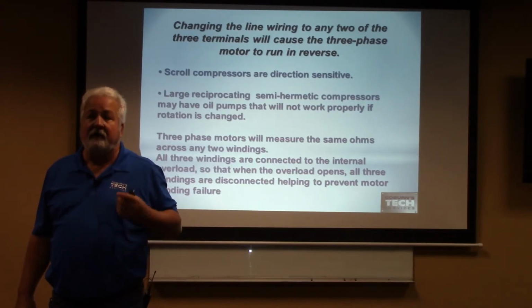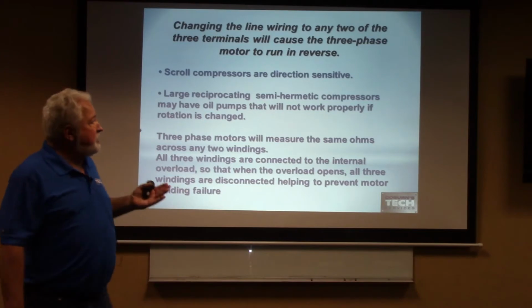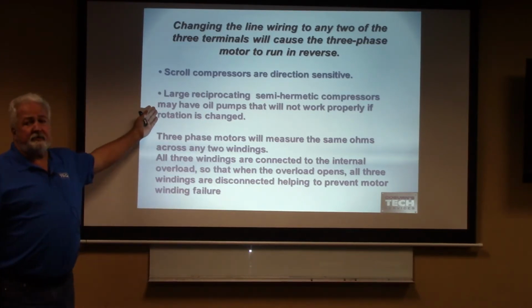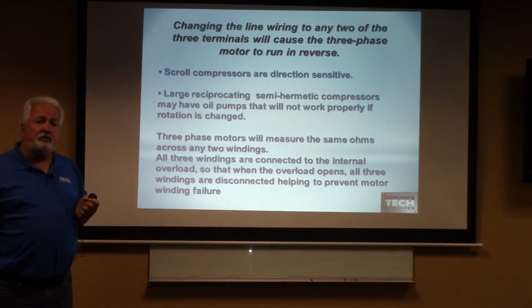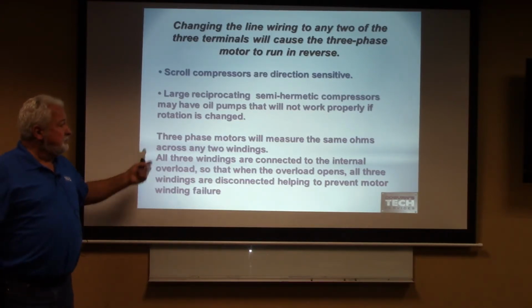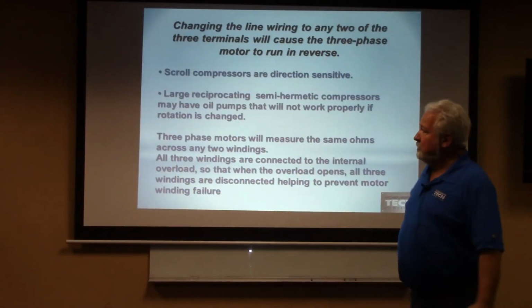It sounds bad. The other thing I need you to understand, if you're going to do it on large reciprocating compressors, make sure that the oil pump is turning in the right direction as well, because sometimes you'll run that oil pump backwards as well. So just be aware of that. So you don't want to just start flipping it around until you've checked that as well.